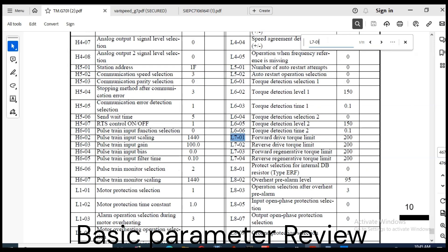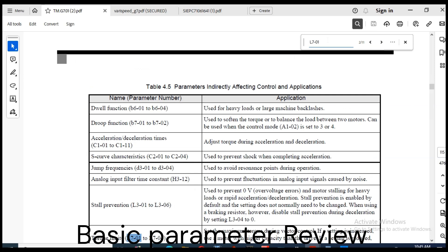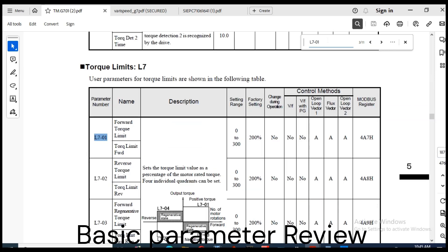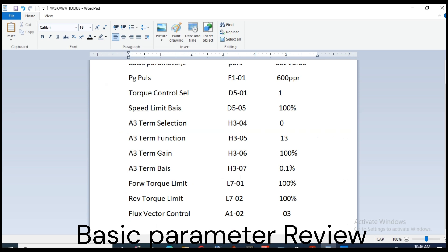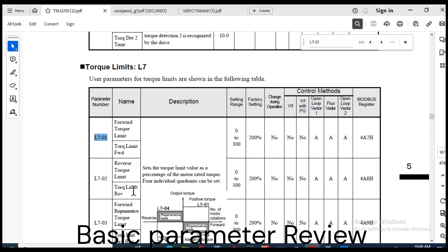Now we set torque limit. L7-01 forward drive torque limit is set to 100%. After this we also set reverse drive torque limit. L7-02 reverse drive torque limit is set at 100%.